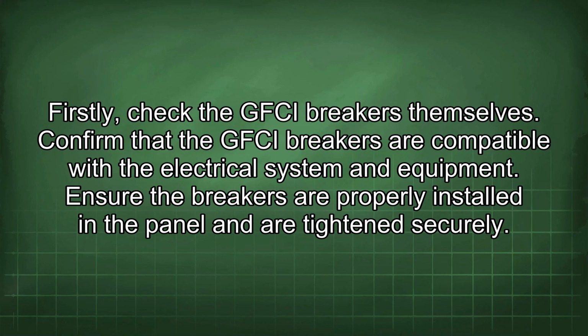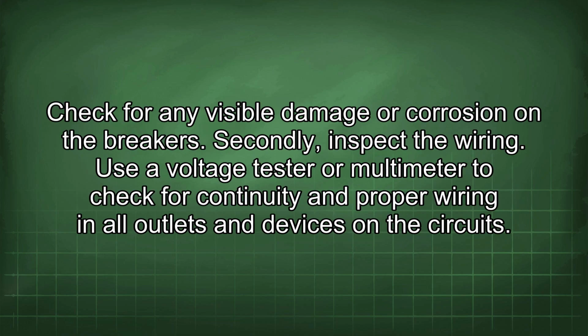Firstly, check the GFCI breakers themselves. Confirm that the GFCI breakers are compatible with the electrical system and equipment. Ensure the breakers are properly installed in the panel and are tightened securely. Check for any visible damage or corrosion on the breakers.